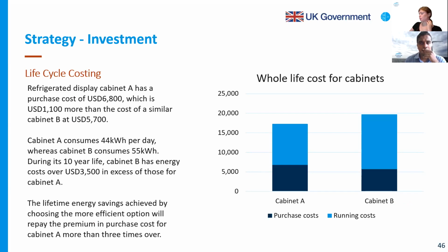So if you assume that the cabinets have a life cycle of 10 years, then within this period, you can see that cabinet B has energy costs of over $3,500 more than that of cabinet A. So what this means is that the lifetime energy savings that are achieved by choosing that more efficient option will actually repay that price premium in the purchase cost for cabinet A more than 3 times over. Next slide, please.